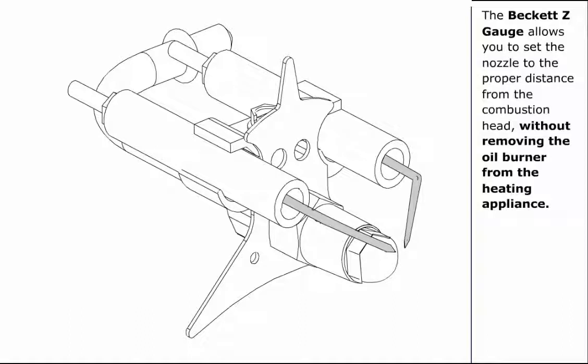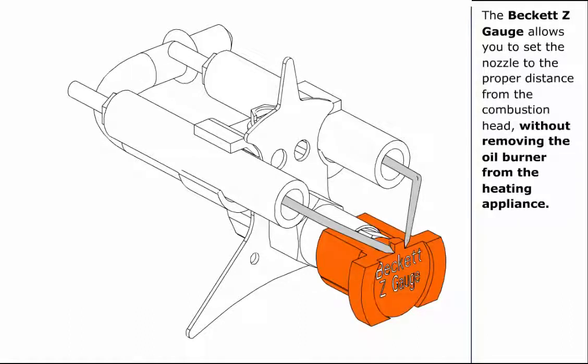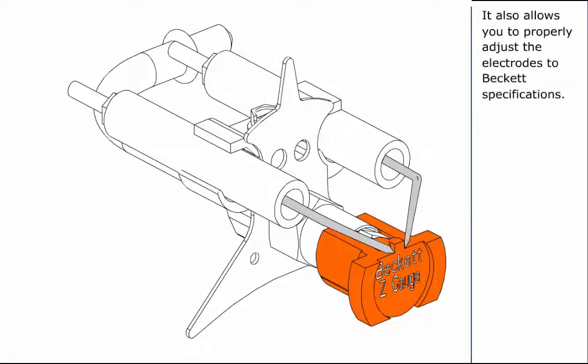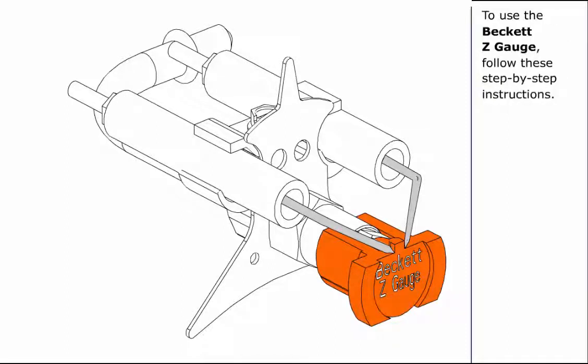The Beckett Z gauge allows you to set the nozzle to the proper distance from the combustion head without removing the oil burner from the heating appliance. It also allows you to properly adjust the electrodes to Beckett specifications. To use the Beckett Z gauge, follow these step-by-step instructions.